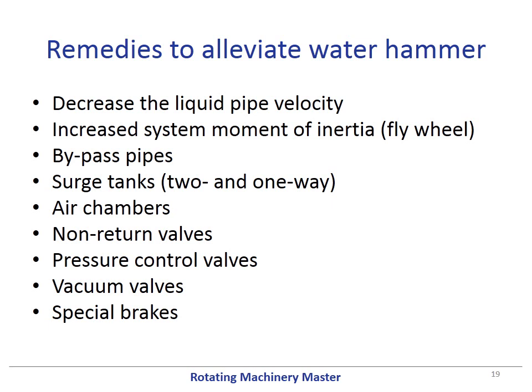These are some remedies to alleviate water hammer. One can change the design to decrease the liquid pipe velocity, or use systems with an increased moment of inertia with flywheels, or use bypass pipes, or surge tanks which can be two-way or one-way, air chambers, non-return valves, pressure control valves, vacuum valves, and special brakes.